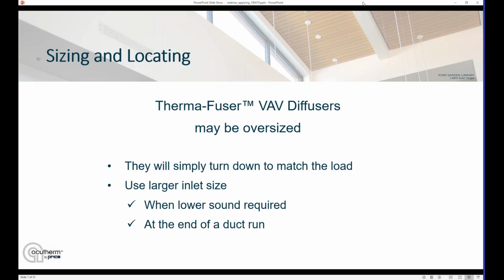Oversizing can also be a good design tool to use. So when you're working toward the end of the duct run and you're starting to run out of pressure, you can upsize the diffuser and get the same volume of air at a lower pressure. This technique can also be used if you're looking to design a very quiet system or the customer's placed a sound design criteria on you. By lowering the pressure in the system, you can lower the noise in a system, and then by oversizing the diffusers, you can still get the same air volumes and meet those design load requirements.